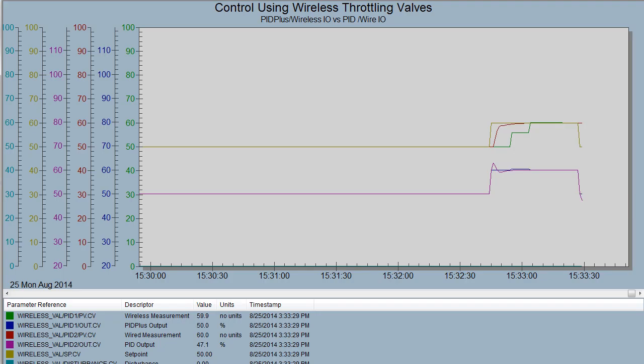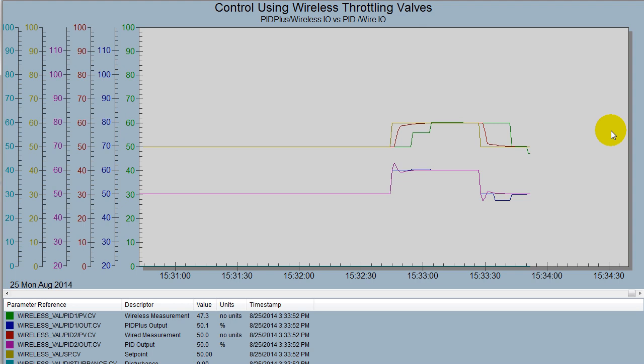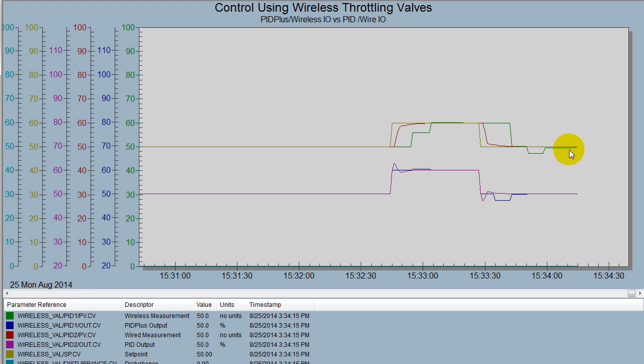We can examine the response for a change down in setpoint and look at the behavior. The response is very fast both for the wired and wireless, and the wireless comes exactly to the same setpoint and valve position as the wired. The response initially is a little bit different, but overall it's very similar. The delay response is only due to the communication delay to our valve. After that initial response, we notice that the wireless measurement — as soon as it's updated — shows we're exactly at setpoint. The delay we're seeing is just due to the fact that we're within 1%, so it takes 16 seconds, the default time, for that measurement to be updated.